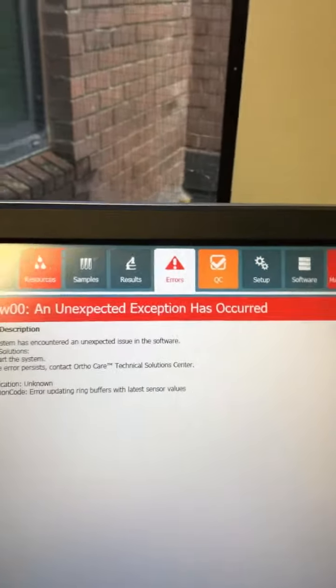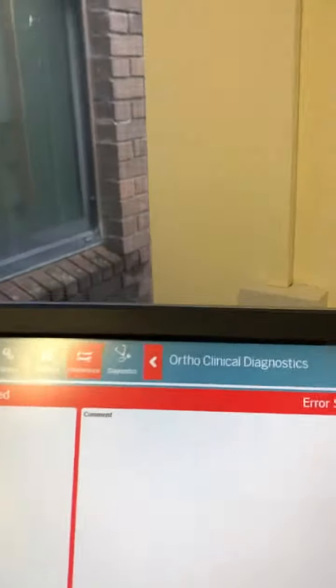Okay, so the first thing we have to do is we'll just kill the power. Okay, our positions. So the first one we're going to do is the main cover. Not the main cover, sorry, this is the sample door sensor. So I'm just going to move this around just to make sure that it's free to move. I'll take my racks off at the same time. But I'm happy that it's free to move. Okay, so internally in our reagent position, just make sure that this is free to move. And at the same time, I will take off my reagent racks. Okay, and that is free to move. And the main reason that I take off the racks and the samples is it speeds up initialization. So I'm happy with that.